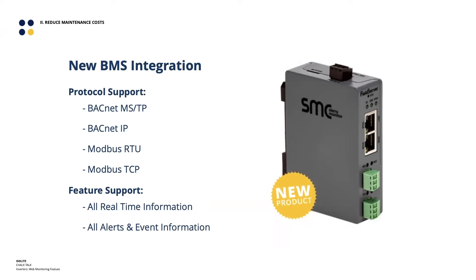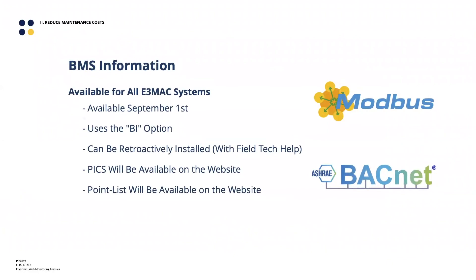All the real-time information, current alerts, and historical events can now be passed over to the existing BMS system. This will be available as of September 1st — you'll start to see the BI option show up in E3 MAC model numbers. Notably, it can also be retroactively installed because of the FieldServer appliance strategy — it can be done on units already installed in the field. We'll ask that a field technician help with that since there's some firmware work required, but if you have a previously supplied job that needs BMS integration, we can absolutely retrofit it.